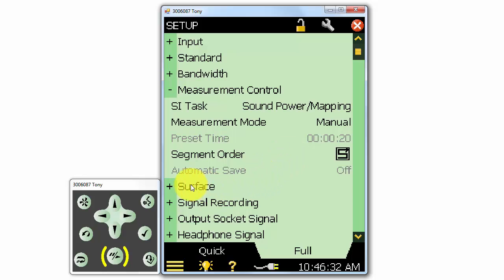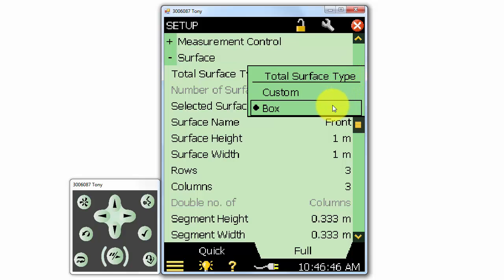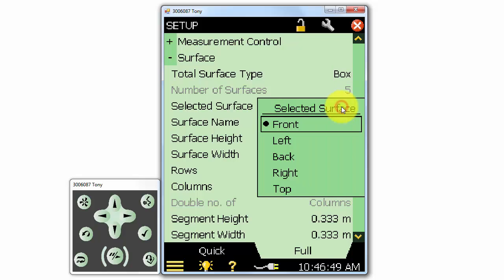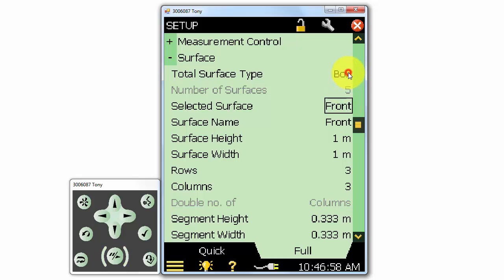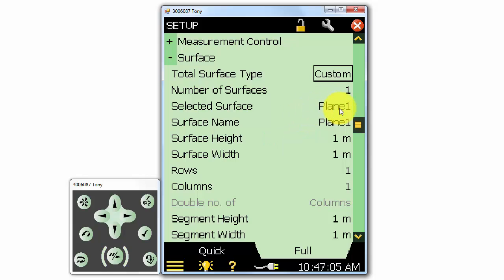Next, we can define the measurement surface. When we make a sound intensity measurement, we measure a reference surface area. A box is the default measurement surface type, and it will treat the measurement surface as a five-sided surface with a front, left, right, back, and a top. If we select custom, we can select a wide range of surfaces, each with different dimensions. For this demonstration, I'll be measuring a loudspeaker that is the shape of a box, so I'll use the box surface type.